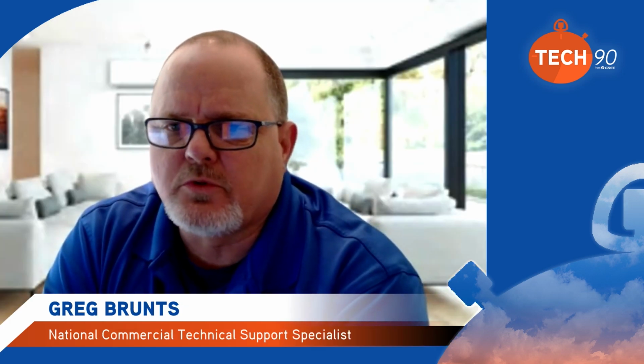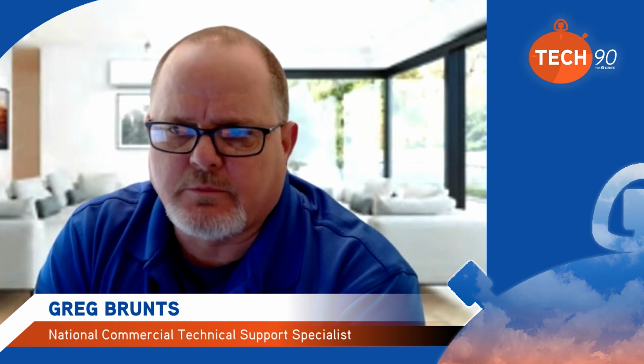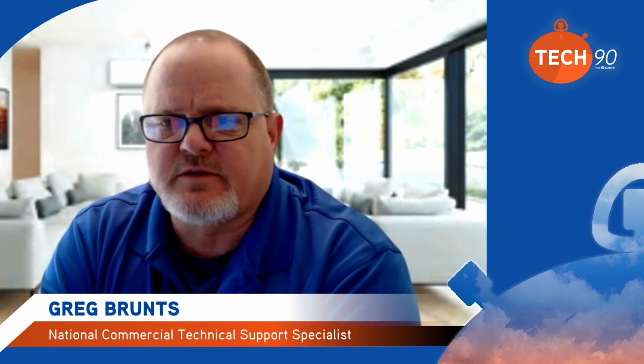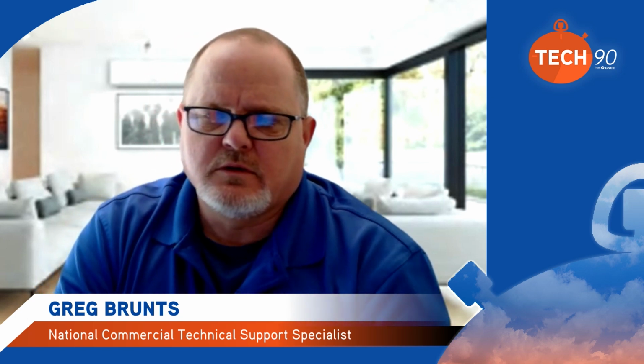And so we have Cecil. He was asking, when you use one controller to operate multiple indoor units, will each indoor unit read and control the set temperature asked for? Well, when you're using one controller to control multiple indoor units, they're all going to have to carry the same set point. You're not going to be able to set separate set points for each one.